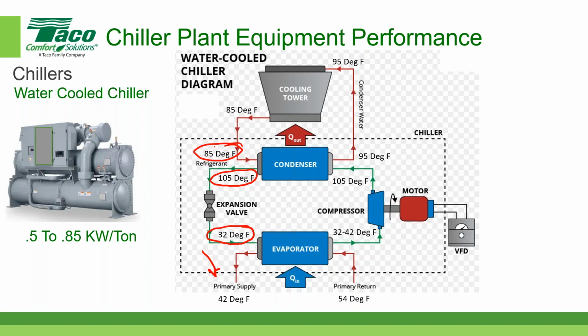So the temperatures that we're mostly interested in here are the refrigerant temperatures, because this determines how much work the compressor has to do. And if you'll notice, it doesn't matter which side of the condenser or evaporator that we're on. We're going to make sure that we have a low enough temperature. I can just cross out 42 for now. So our refrigerant temperature wants to be around 32, perhaps a little bit higher than that, and that's when we call it superheated, and that's to make sure that we have gas in the compressor.